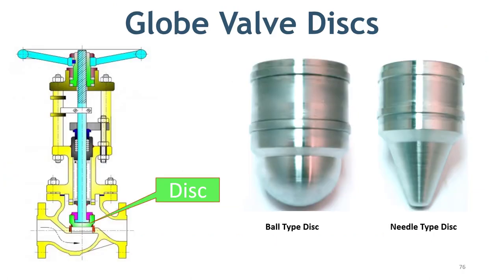The next part of the globe valve is the disc. You should know that all movable and replaceable parts of the valve are collectively known as trim. This disc is available in different shapes and designs, and here you can see some of them. Each disc type has a specific function — for example, a ball-type disc is used for throttling, whereas a needle-type disc is used where fine flow control is required.